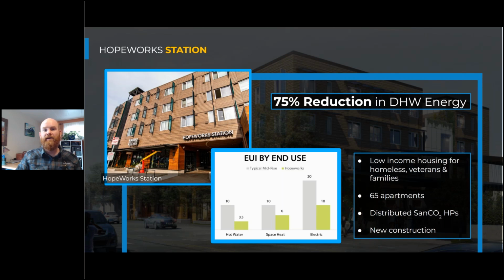And so that had a huge advantage on first cost of piping, as copper pipe, stainless steel pipe is really expensive right now, but also reduced the distribution loads associated with that temperature maintenance system or the hot water circulation system. So there are a few things that really worked out well there and made sense. It does mean that there's a few more maintenance points for those maintenance personnel, but typically with split system heat pumps for space conditioning, they're familiar with the maintenance procedures that a heat pump water heater needs as well, cleaning an air filter and making sure it's operating efficiently and effectively and not clogged up.